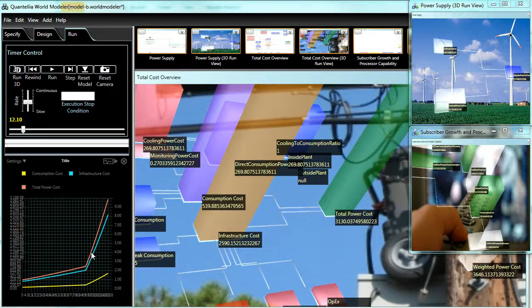So even though we might invest in equipment that can sleep from time to time, and therefore we can reduce this consumption cost factor, it's important to realize that the infrastructure cost is driven by the peak rate in this case, because of course we need to build out cooling in facilities that can support that peak rate. So yes, we can get some benefits from sleep mode equipment, but it is a smaller relative benefit than if we don't do peak shaving, if we don't figure out a way to reduce our peak consumption so that the overall cooling and facilities infrastructure costs are reduced.